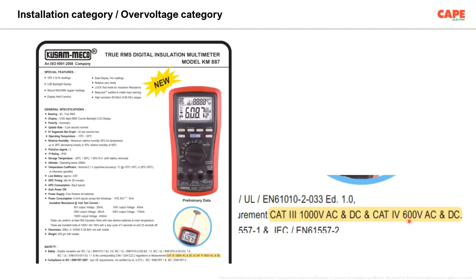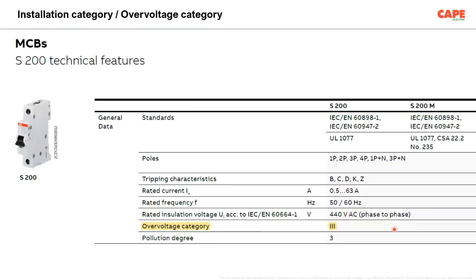maybe is the question which comes to your mind. Yes, 690 volt is used in several industrial applications. Say, for example, all the large wind turbines working in India, from 200, 300 kilowatt onwards. Nowadays, the wind turbines are even 2-3 megawatt. So for all these wind turbines, the connected line is at 690 volt phase to phase. So if we take this particular multimeter, it says for that particular application, you cannot use this multimeter. That is how it is.